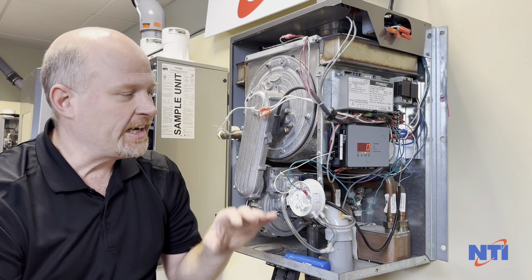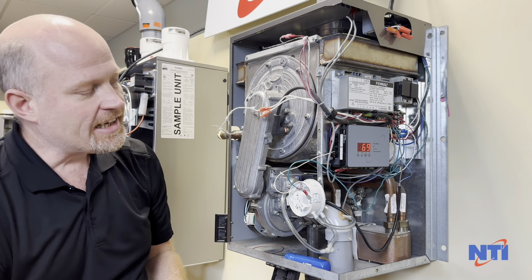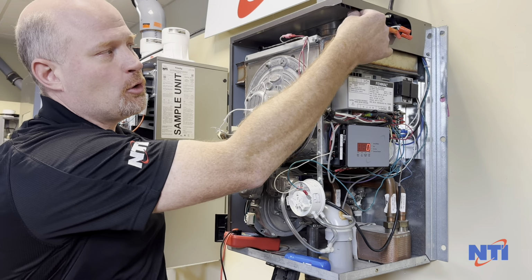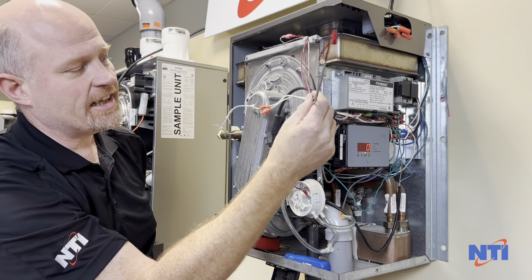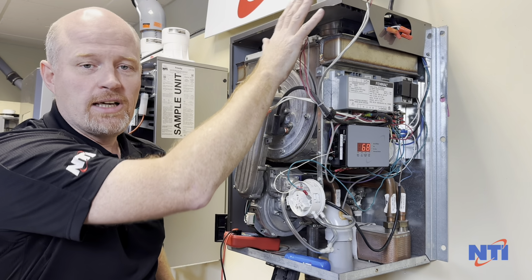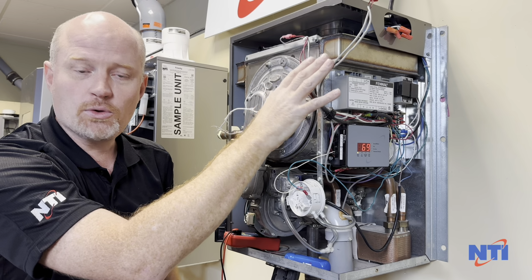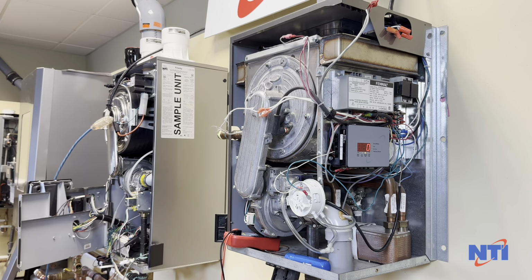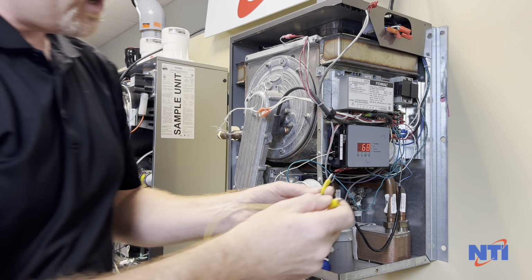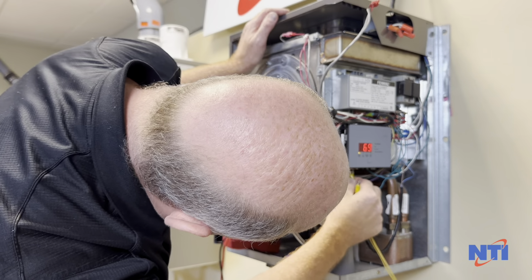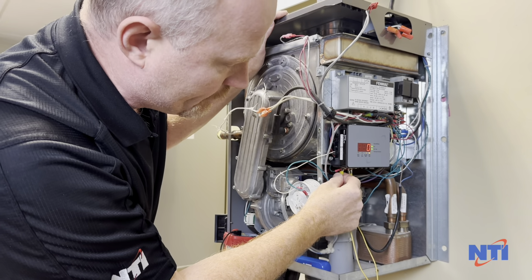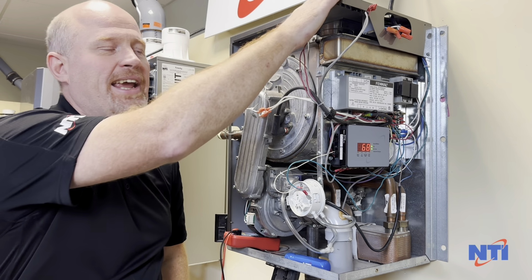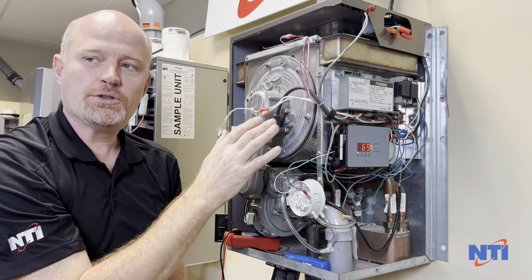If you've checked all that stuff and it's still doing the same thing, the very last thing you can do, and this is fairly rare, but sometimes it happens, pull off this red plug at the top of the boiler. What that's going to do is remove any external demands from thermostats, from aquastats, outdoor sensors. And then using a jumper wire, just grab my jumper here. Using a jumper wire, manually jump out the call by jumping A and C on the bottom of the Sentry, or C and T. If the problem goes away when you do that, you may have something external that's applying a voltage to the boiler.